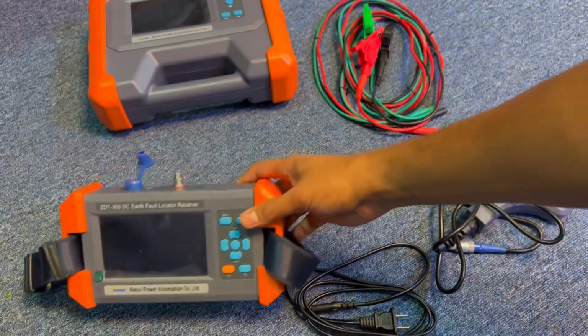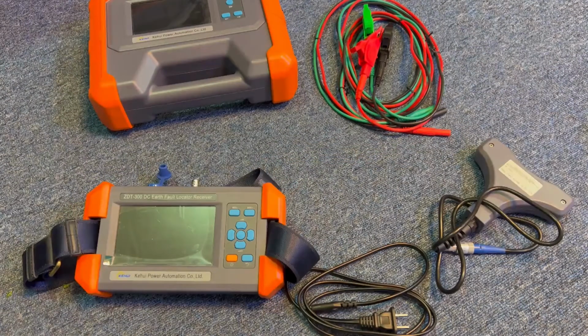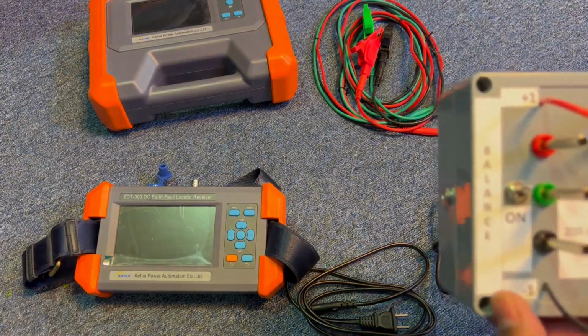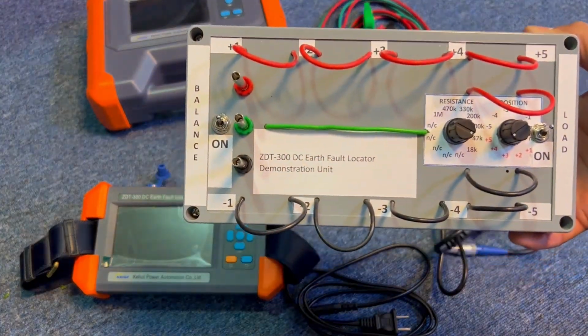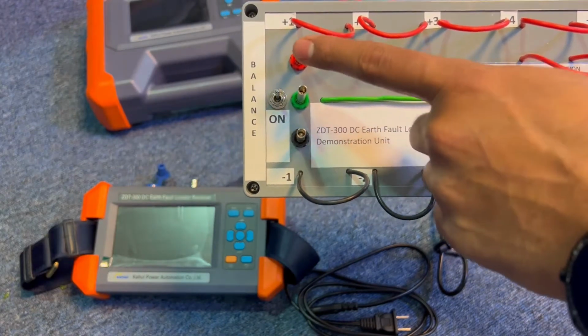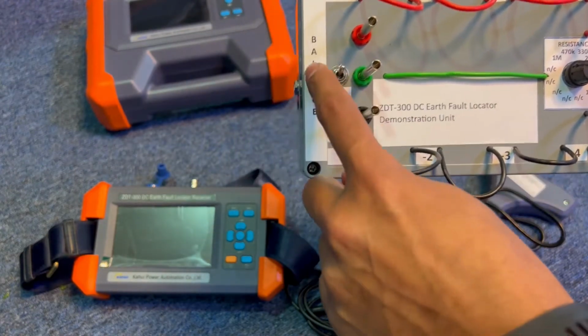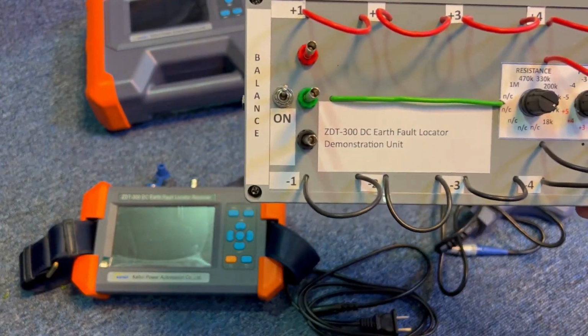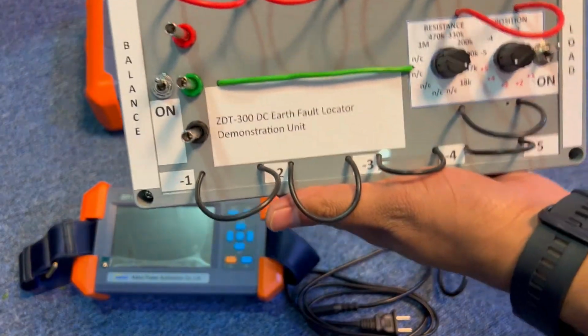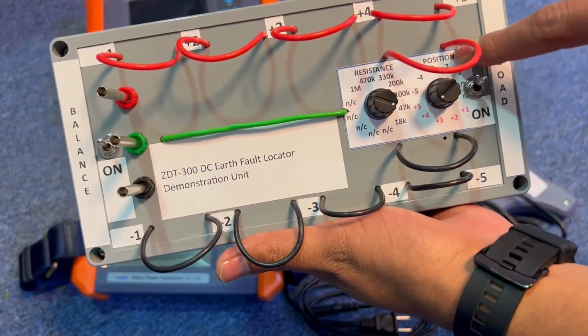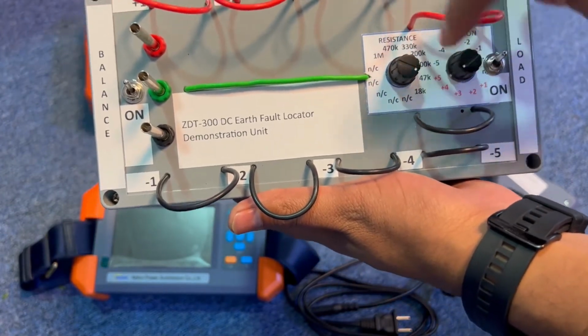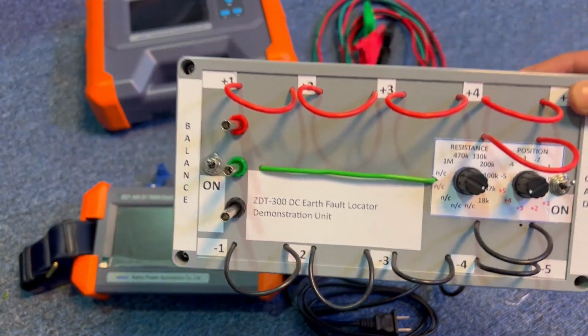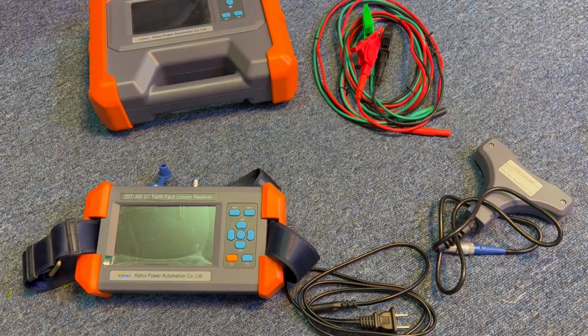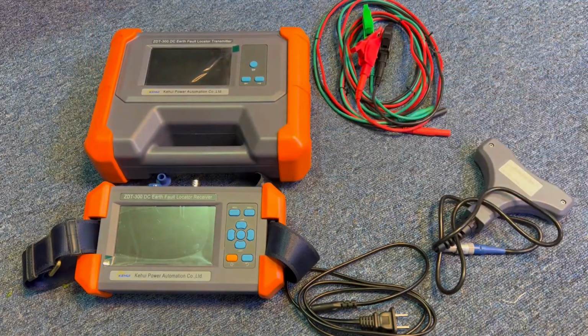So let's have a small demonstration of how it works with the DC power supply. We have created a DC system model, which we call a simulator, where you can see a positive bus, a negative bus and a ground, and we have a balancing circuit which divides the voltage equally in half. This is a 20 volt DC system, and we have created different faults, whether positive or negative, of different resistances. So you can see exactly how this equipment will give you the complete information of the DC system, including the fault resistance to ground, the balancing resistance of your DC system, and also the capacitance to ground on the DC system. So now let's start.